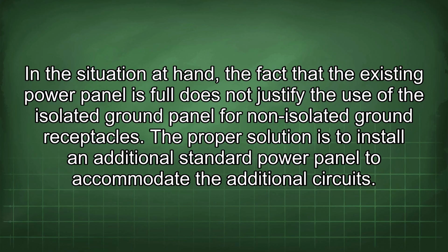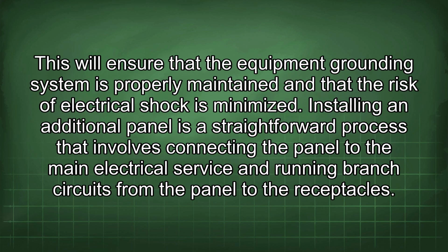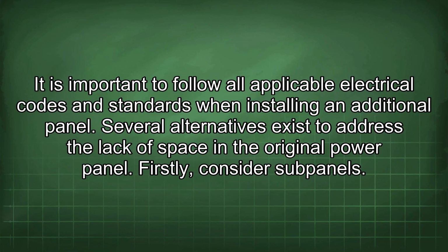In the situation at hand, the fact that the existing power panel is full does not justify the use of the isolated ground panel for non-isolated ground receptacles. The proper solution is to install an additional standard power panel to accommodate the additional circuits. This will ensure that the equipment grounding system is properly maintained and that the risk of electrical shock is minimized. Installing an additional panel is a straightforward process that involves connecting the panel to the main electrical service and running branch circuits from the panel to the receptacles. It is important to follow all applicable electrical codes and standards when installing an additional panel.